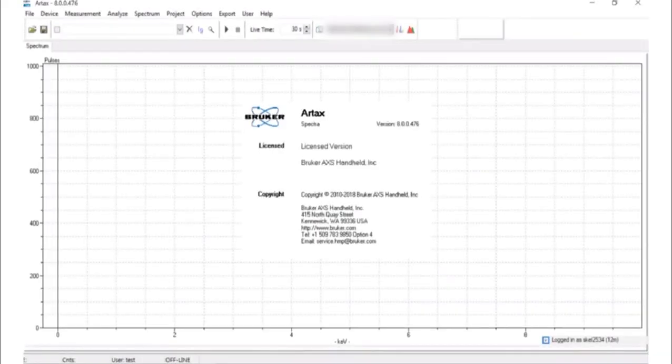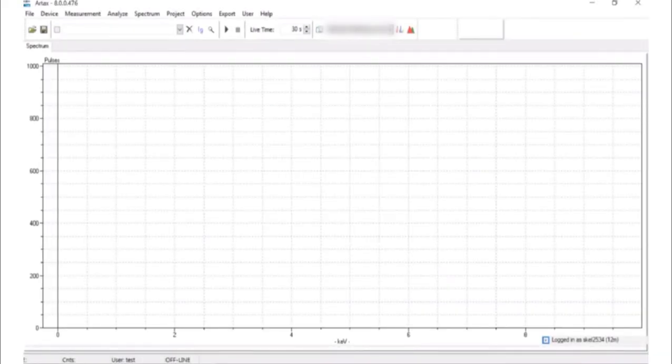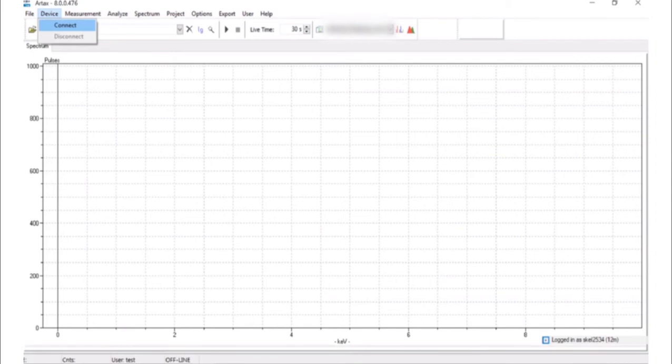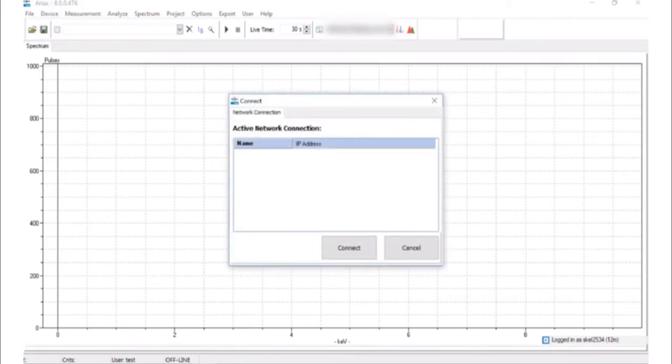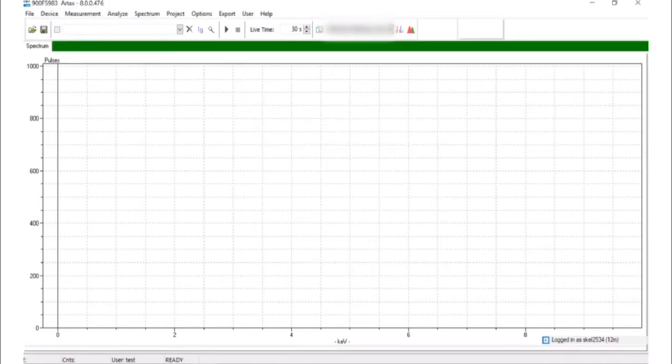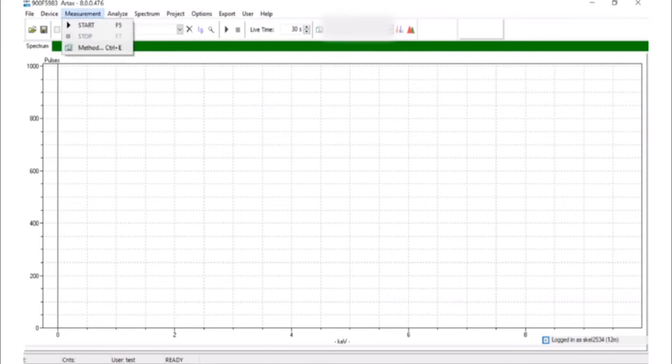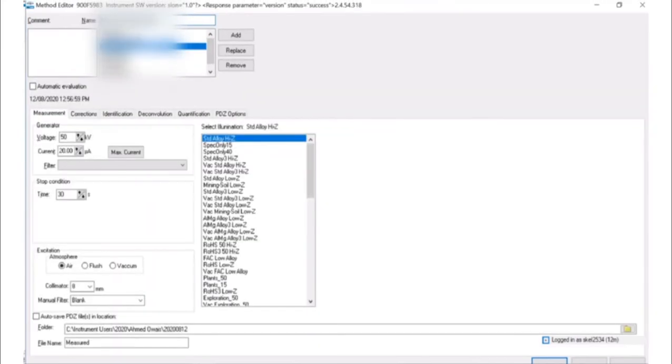Open the Artax software. On the toolbar under device, select connect. A box will appear with the instrument serial number and IP. Click connect. When the instrument and computer are connected, a green bar should appear. Open measurement method to bring up the method editor.